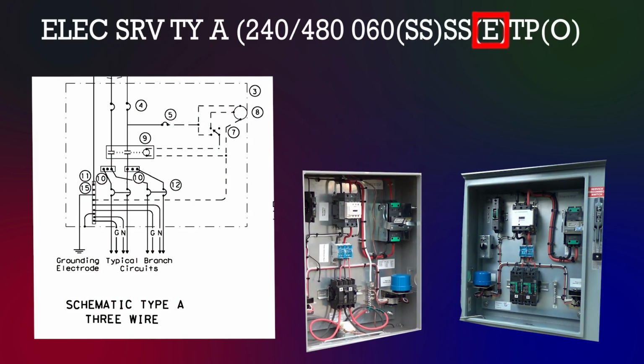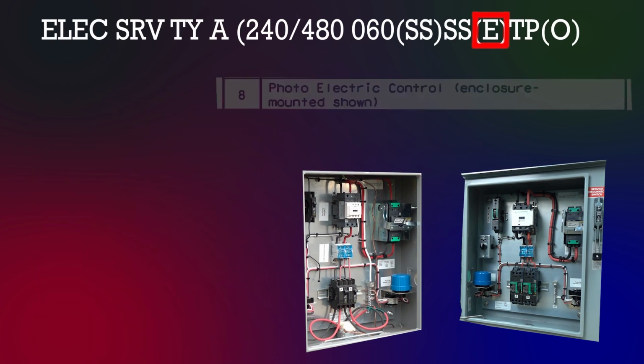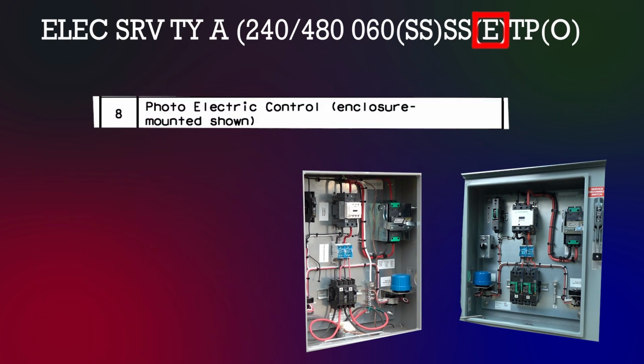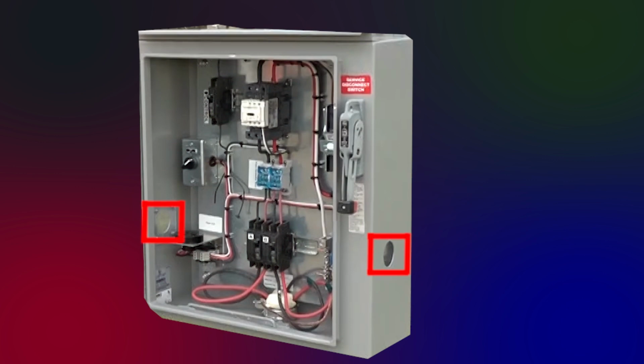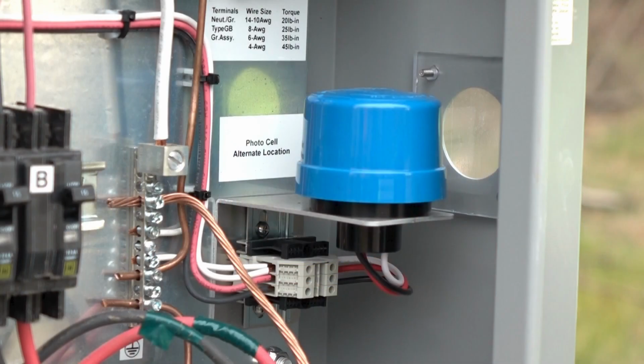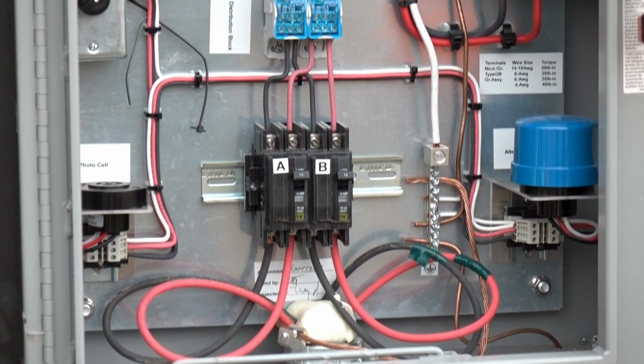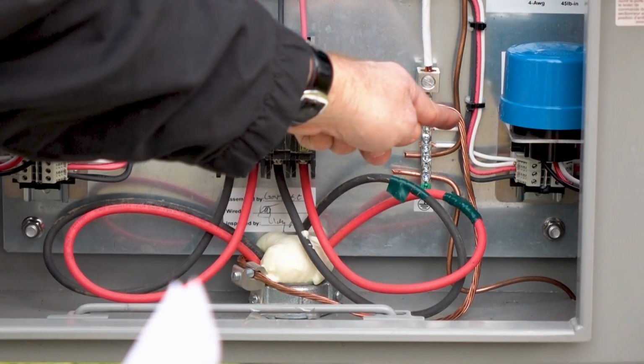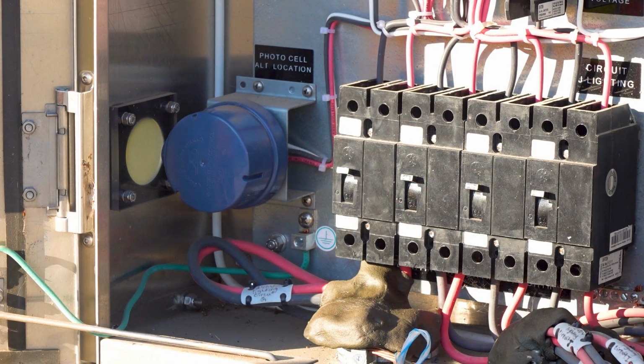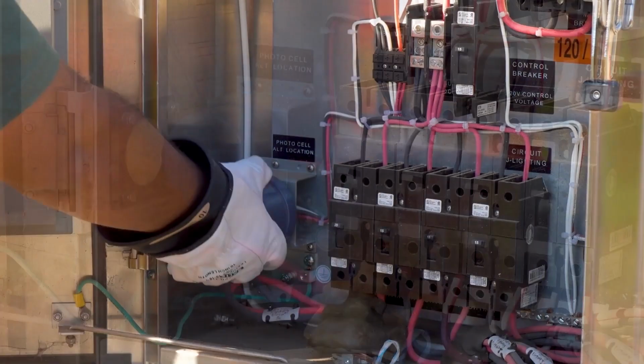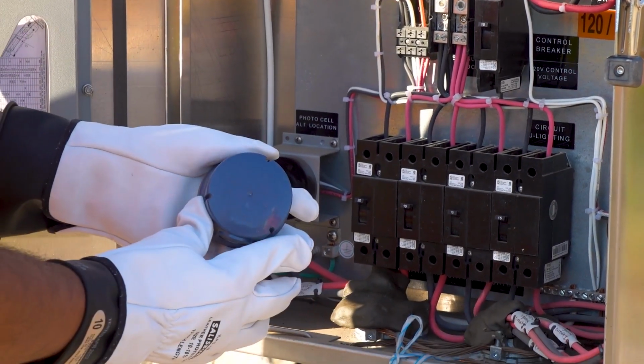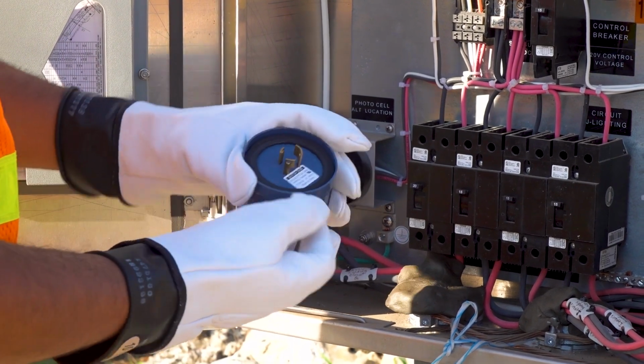The photoelectric control, or photocell, may either be mounted in the service enclosure or external to the Type A service. The inspector will need to review the descriptive code for the service being inspected to determine the photocell location. When the photocell is specified by the plans to be installed within the service enclosure, the UL panel shop is required to provide 2 photocell viewing windows, one on each side of the panel. There must be adequate space within the panel to locate the photocell eye in front of either window. When the photocell is enclosure mounted, the photocell can be removed by rotating the photocell with one hand while holding its mounting socket with the other, and then pulling the photocell out of the socket.